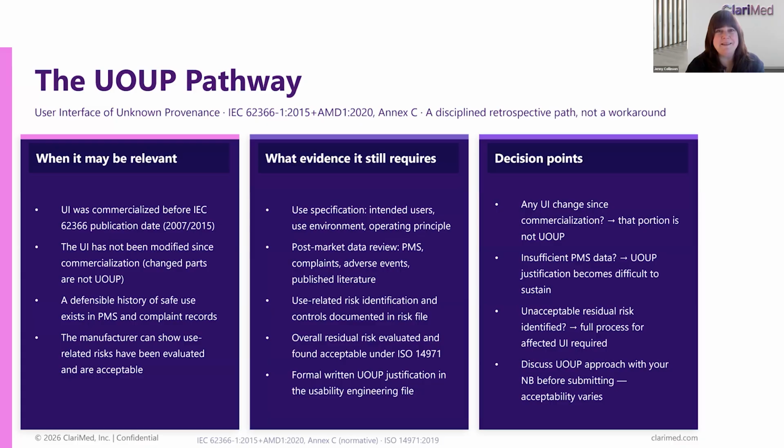I mean, it completely depends what format you've drafted your use risk files in. But typically, we would say that for a device, it was something that could result in serious harm upwards. So only looking at severity and looking at things that would result in serious harm or death. And so this is for Europe specifically. That's where I would go for that.